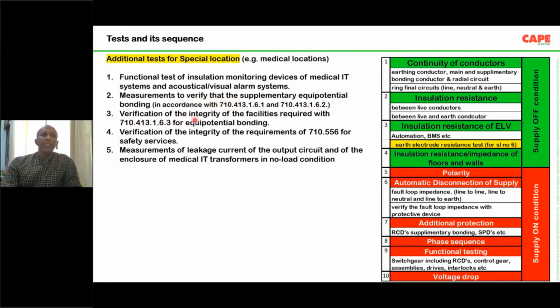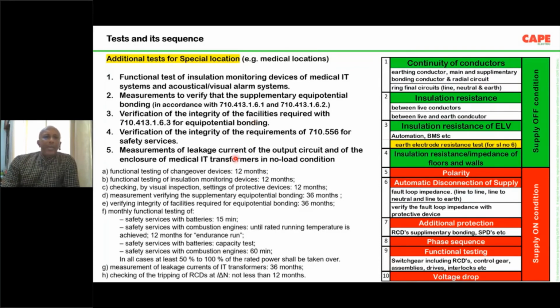And the third one, verification of integrity of the facility required with these particular clauses of the standard for equipotential bonding. So everywhere the standard is talking about equipotential bonding. That means all metal things in your building shall be connected together so that there is no potential difference between different kinds of equipment. And the periodic testing, the functions, the different periods are also made in the testing. Now coming back to supplementary equipotential bonding, I made a statement that every apparatus and equipment in the hospital shall be interconnected together. What do you do for a medical equipment?